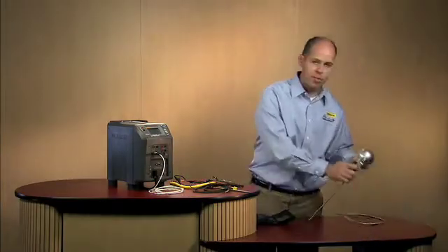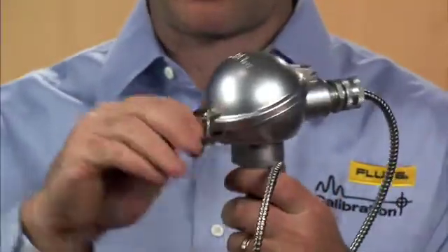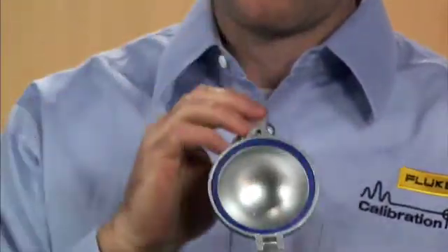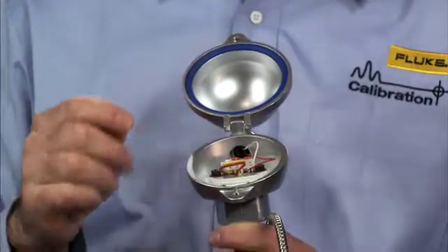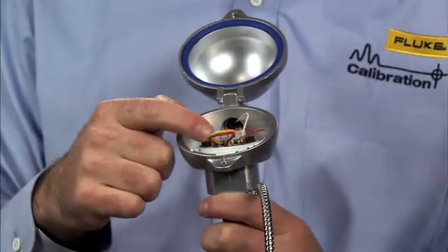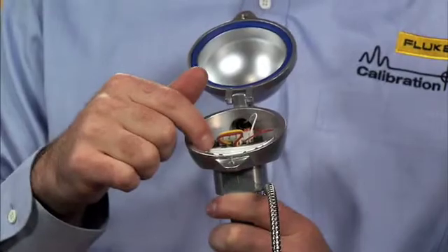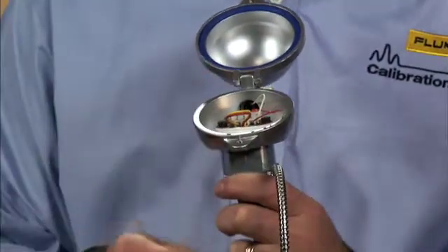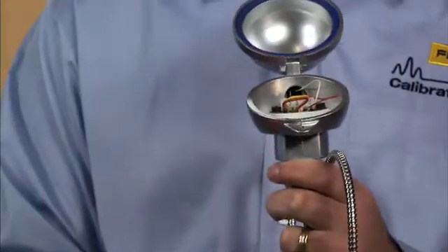Now here I have a very typical transmitter. This is a thermocouple transmitter. If I open up the cap here you'll see that we've got a type K thermocouple connected up. This is the transmitter itself. With the wires coming out we're measuring milliamp current.